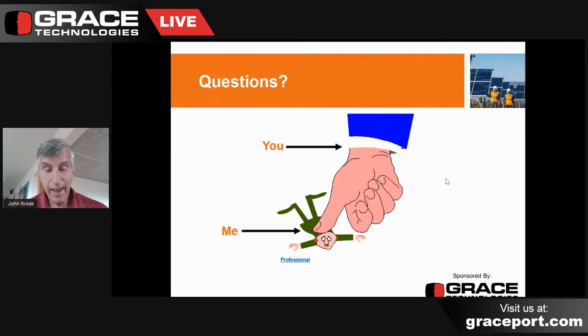Well, the switches don't add to fault current; they just conduct fault current, and so they're just one series element in the circuit. You can visualize it as if you just took the switch out and pasted in a solid bus bar. So labeling them is not what I want; whatever the equipment is that they're actually working on is where I want the label, not the switches that feed the particular equipment. So when the worker is accessing the equipment protected by an upstream breaker, I'm interested in both the source and the load side of that breaker itself. And remember, the source side of the breaker will be the same as the load side of whatever is feeding it.